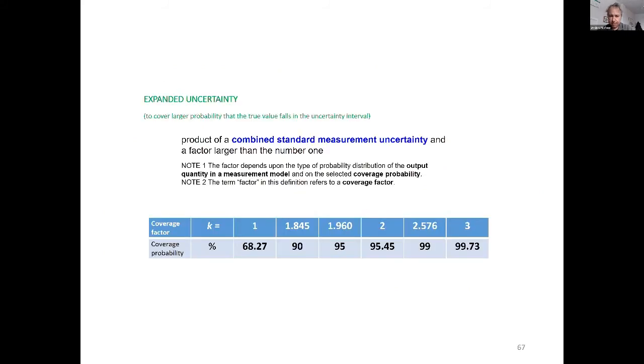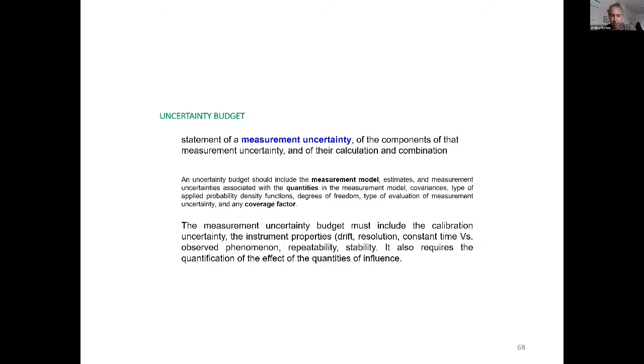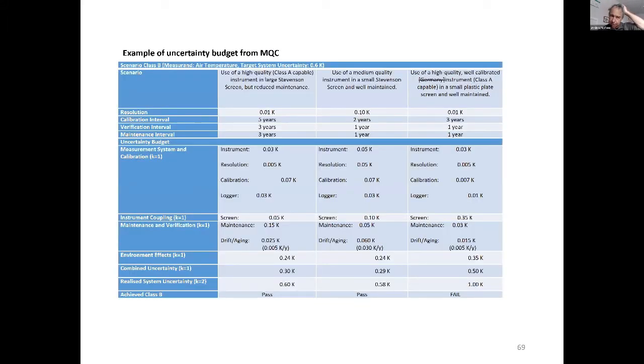We have seen this. For the expanded uncertainty, please use at least a factor of 2. Good practice is that you get all the information in what we call K1, the coverage factor. You make all your calculations, and then you transform at the end into K equal 2, the uncertainty budget. So this is an example of an uncertainty budget, which is taken from the document I was referring to, a measurement quality classification. Take a look at that.